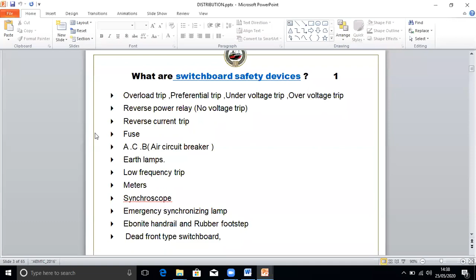What does this dead front type mean? Dead front type means that on the front side of the panel, nothing is accessible; you cannot access any live systems. It is totally closed. Dead front means the front side is totally closed, a sealed type. Here you see the handrail in front of the switchboard; in bad weather conditions and all, you can hold it. It's an insulated handrail.